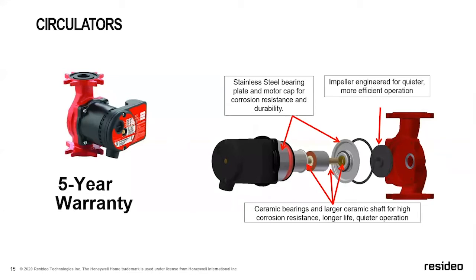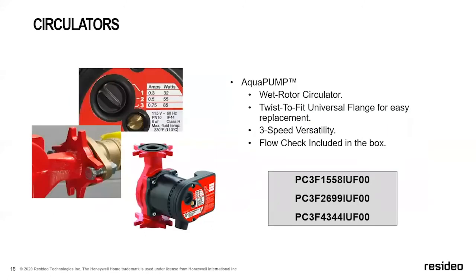You can see that the electrical connections are on the front. So if you're stacking pumps close together, you just get a Phillips screwdriver out and take off the head. You're not working on the side of the pump. You have plenty of room for access. And then the black piece at the bottom, that's actually a threaded fitting. So you can thread in a Romex connector right into it and not worry about having to put a nut on the Romex connector. It takes that place. Installation's super easy.